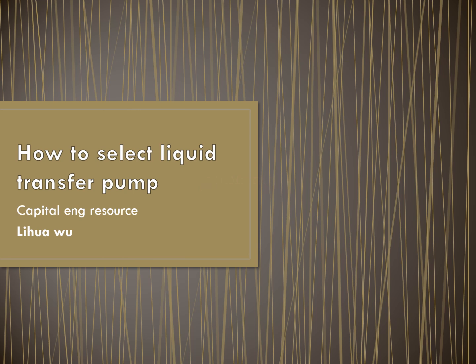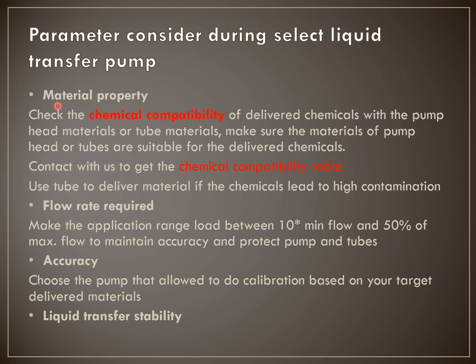When selecting a pump, there are several parameters to consider. First is the material of the pump. You must consider the chemical compatibility of the pump materials with your target transfer chemicals. You need to make sure the materials are suitable for the transfer. You can contact us to reference a table showing what types of pump heads, tubes, or syringes should be selected.